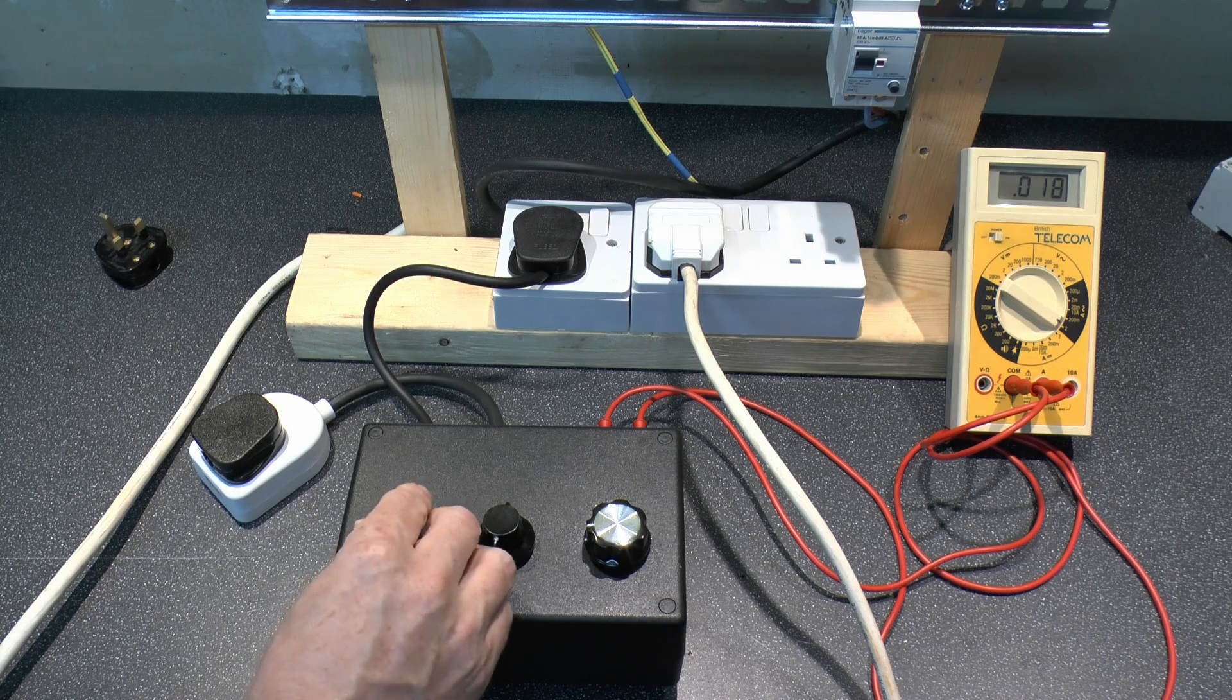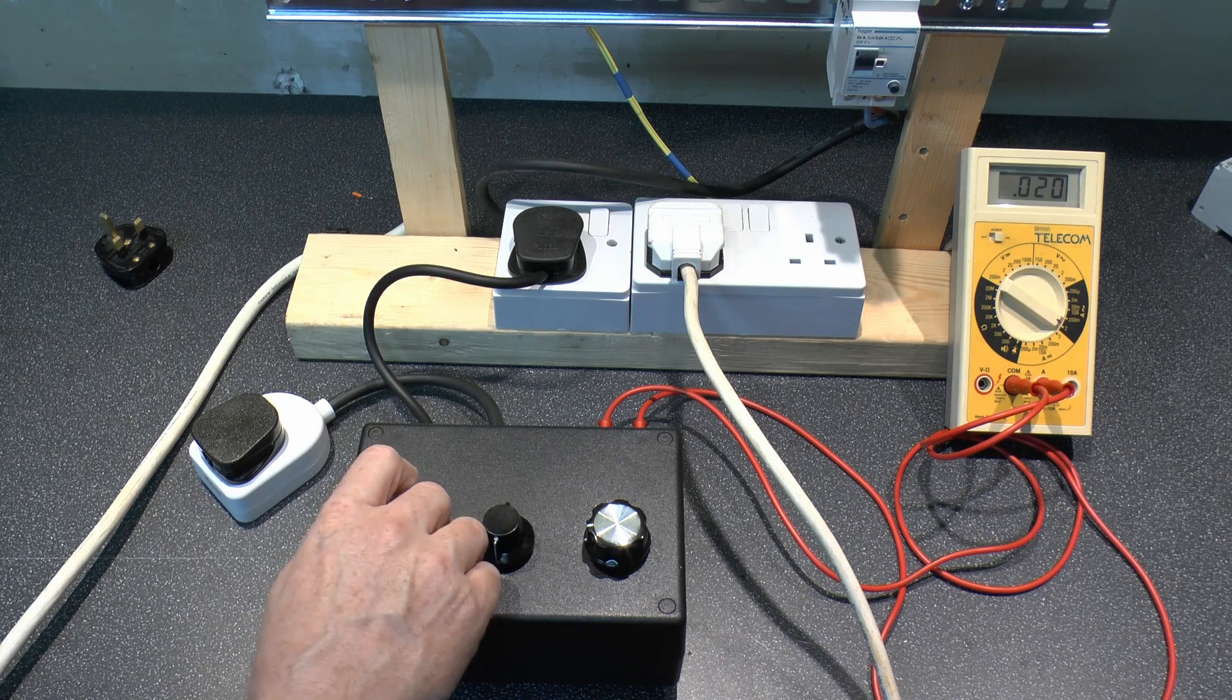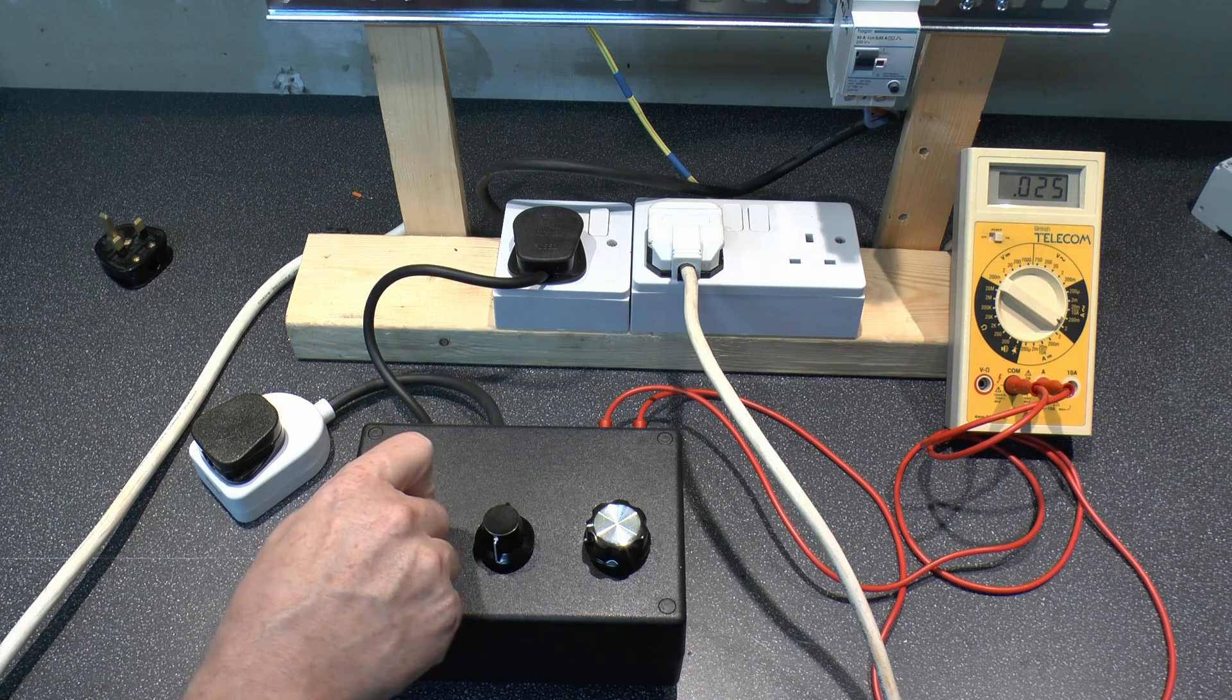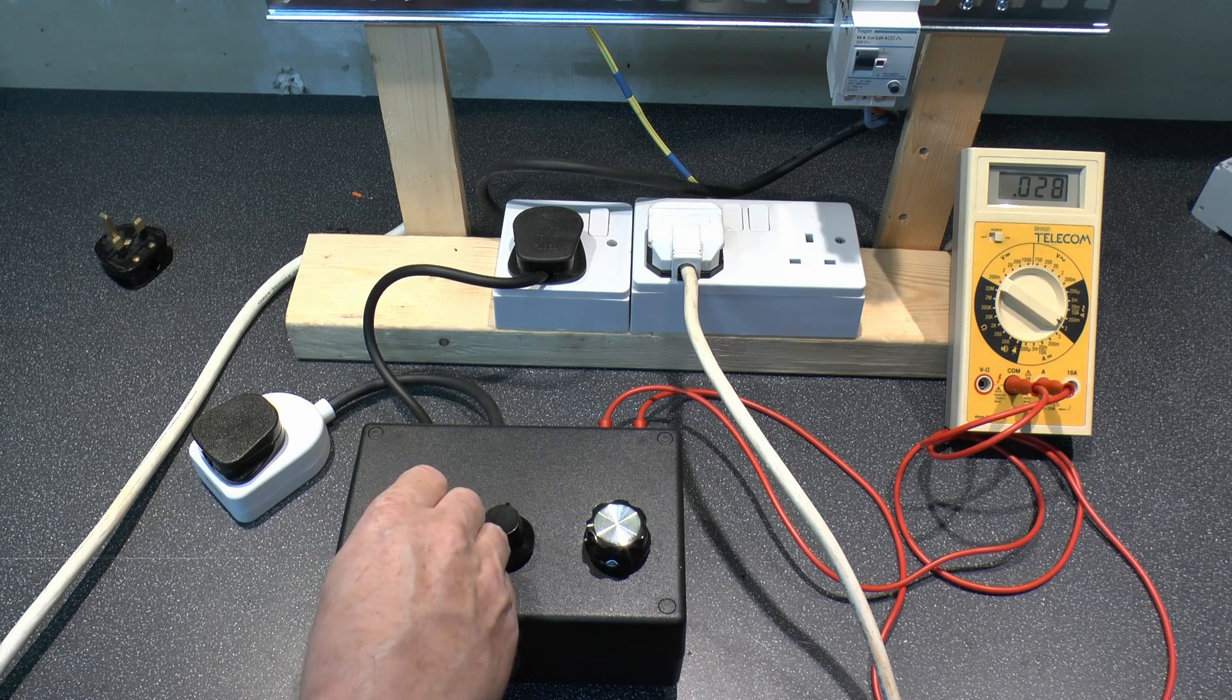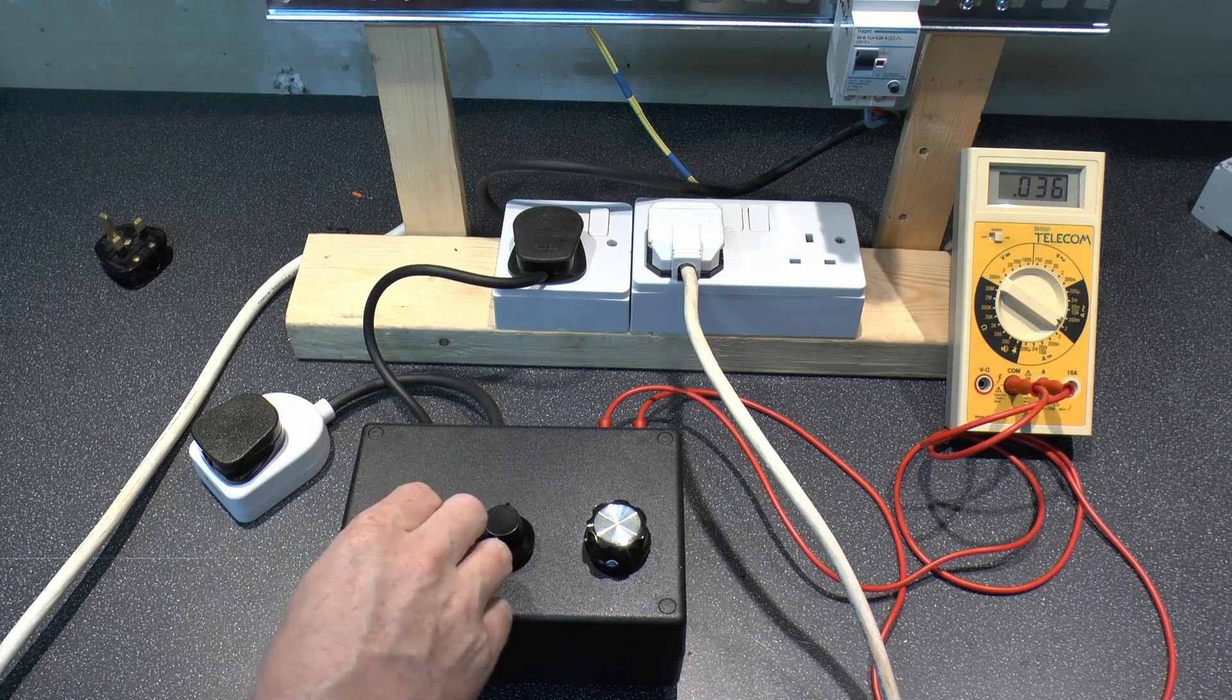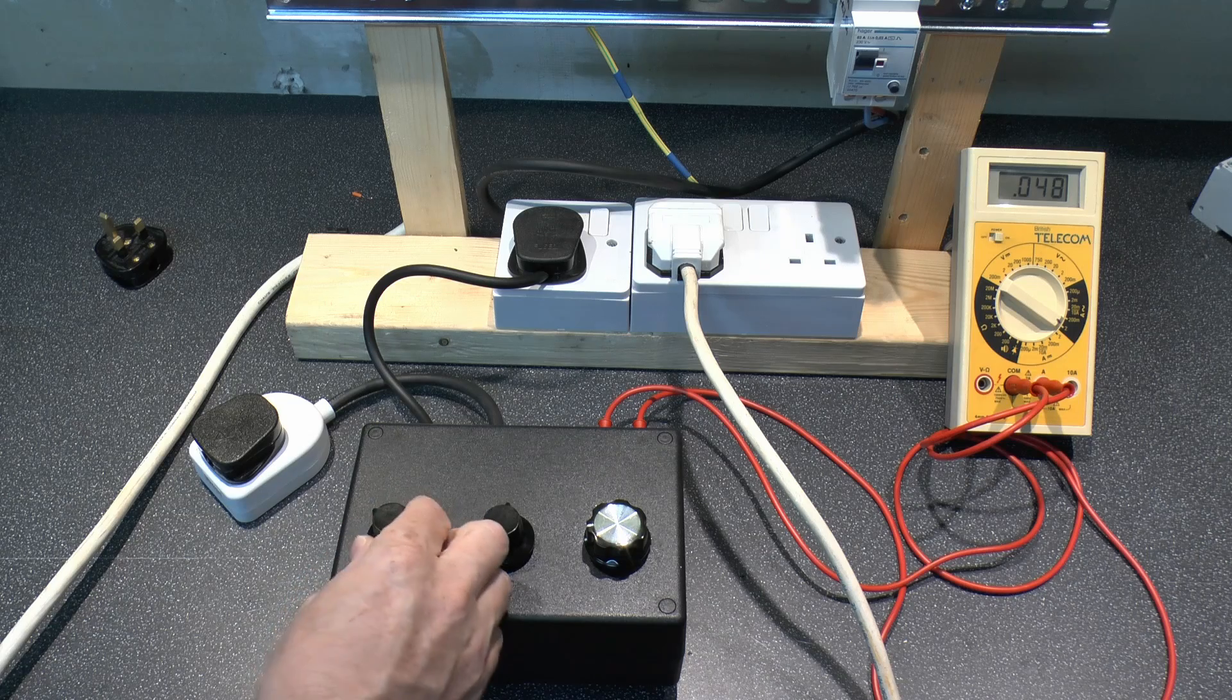Now bearing in mind it tripped around the 20 or 21 milliamps mark previously so we're just coming up to that now. But as you can see we're going past that particular level there so 25, 26. So we're now over 30 milliamps so this is beyond the specification of the device it should have tripped long ago by now. And we can continue turning the knob and increasing the current further.